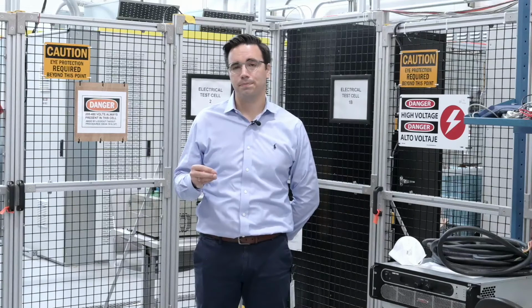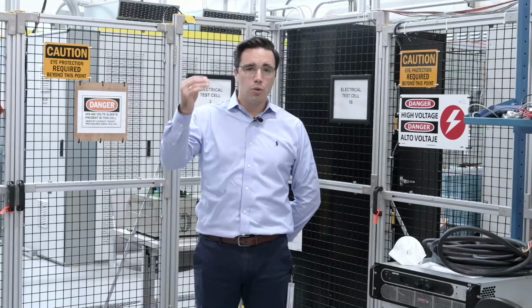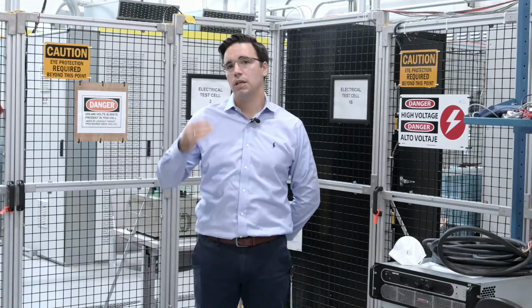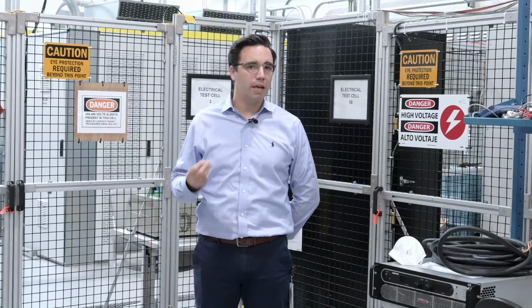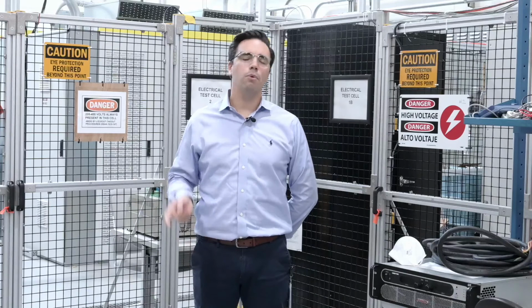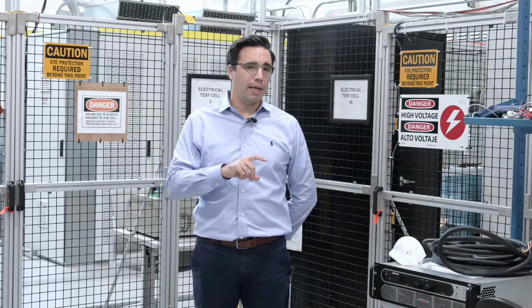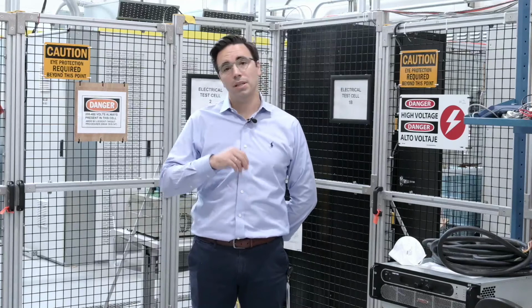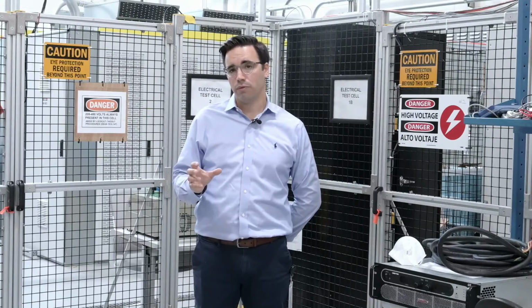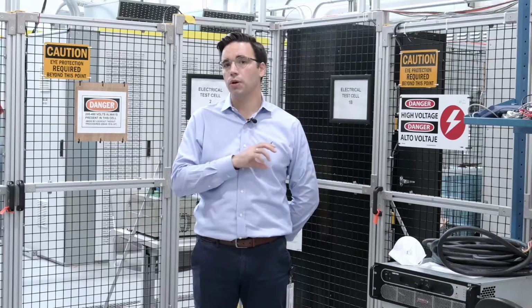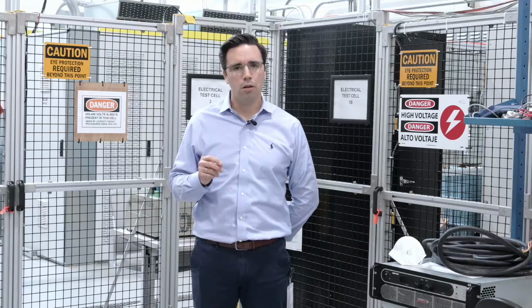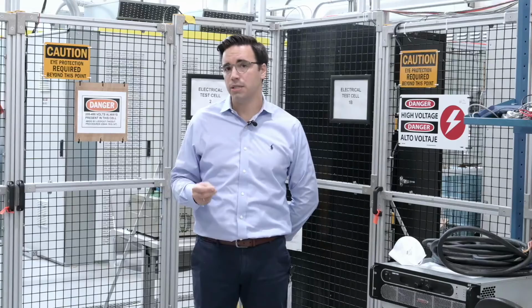We also expect multiple scenarios, so faults close to the main source, faults on the main distribution bus, and faults close to the EV chargers. In all cases, we expect to see very high short circuit currents and especially very fast fault dynamics. When we're looking at ground faults, the situation is a little bit different. On the one hand, we can see that the contributions from batteries and EV chargers can be limited in terms of ground fault current because it can be limited by the power converters. On the other hand, the contribution from the main grid or the main source going through the rectifier will still be there and will need to be addressed by the protections. Overall, we expect very high fault currents and very fast dynamics, and we need to keep this in mind when we think of protections. Okay.